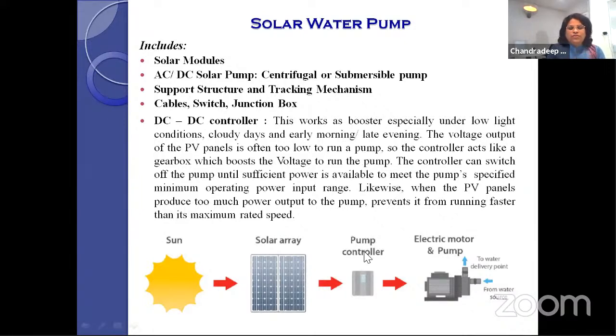Solar water pumps, as shown in the figure, have solar modules forming a solar array, meaning modules connected in series and in parallel, as discussed yesterday. The system has an AC or DC solar pump, which is of two types: centrifugal or submersible, depending on the depth of water. If using a river or lake, we use a centrifugal pump. If the water is deep, below 14 meters, we use a submersible pump, like for a borehole.